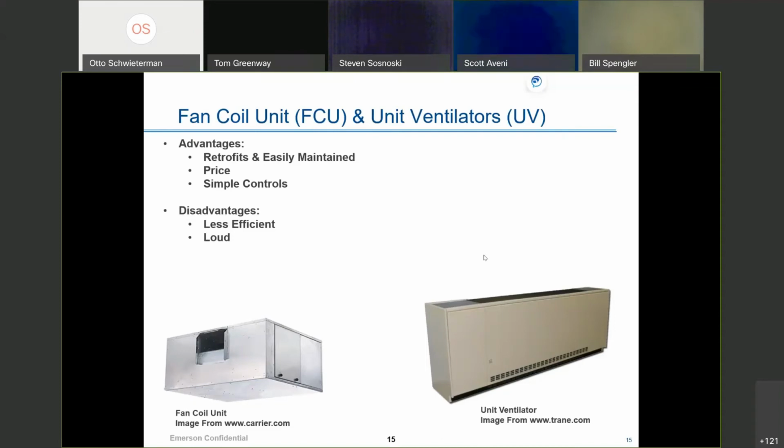It can be annoying, especially if there's a compressor in there, or if it's a digital compressor. You would not want to install a digital compressor in one of these units. That's going to change the sound up and down as it loads. So the sound is a big disadvantage of these types of units, but they have their advantages. If you want to do something cheap and quick, these can help quite a bit.